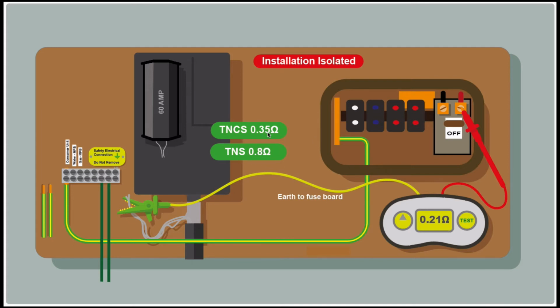If it's TNCS, it's 0.35. That's why it's important to know what your earthing arrangements are, TNCS, TNS, because they have different maximum readings. So we've got our reading. We record that when we use it on our certificate later on. So we're happy that we've got a good earth coming into the property. We've got our ZE reading.